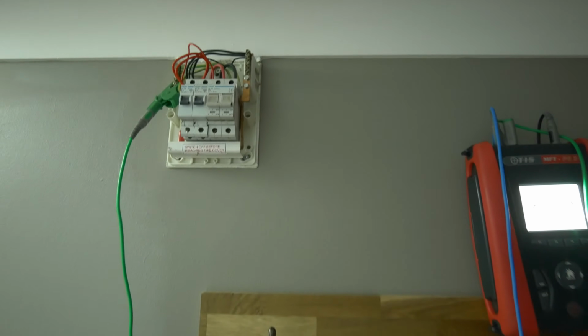We'll get that locked off, and then we'll come back to this board, open it up, and see what we've got inside it. So I now need to get a measurement of ZdB for this little consumer unit, and I'm doing that with the camera down, so I'm nice and safe. I'm onto the earth bar already. I need to attach the probe onto the line, as you can see here with the MFT Pro Plus. So we can do that, and then we'll see what value we get. I'll jump back and show you rather than trying to hold the camera with that board open. So I'm going to put a bit of PPE on, I'll take that measurement, and we'll jump back and have a look at what we get.